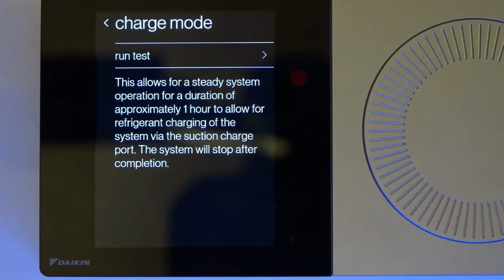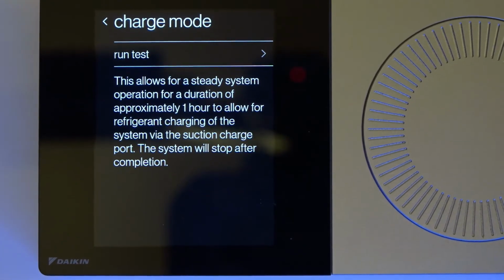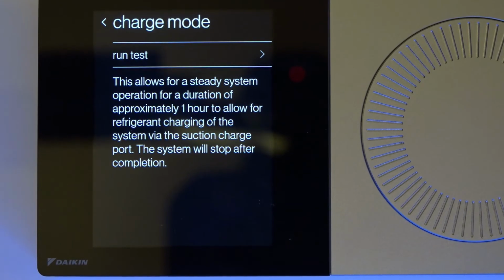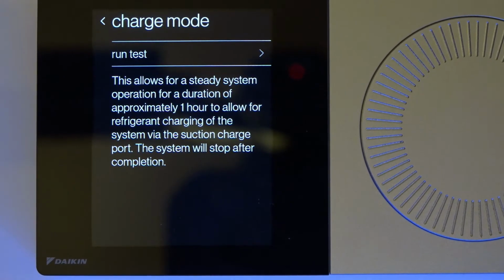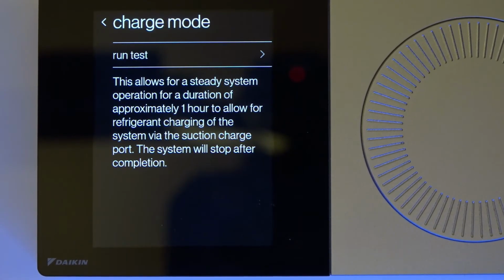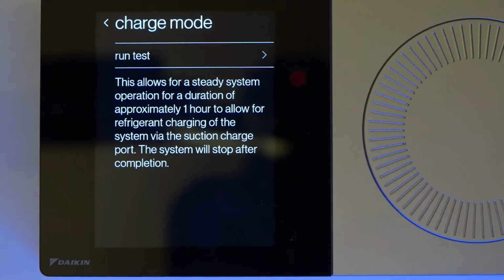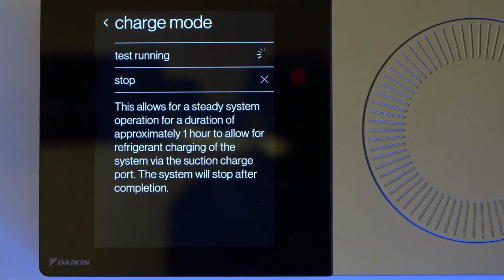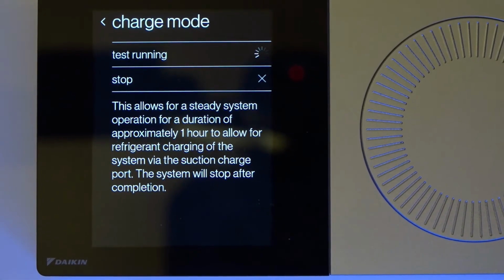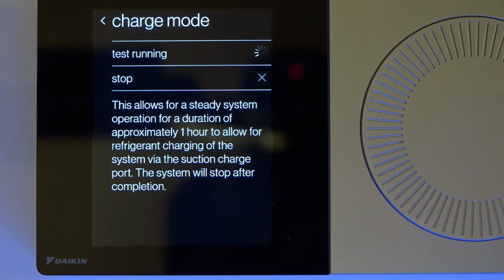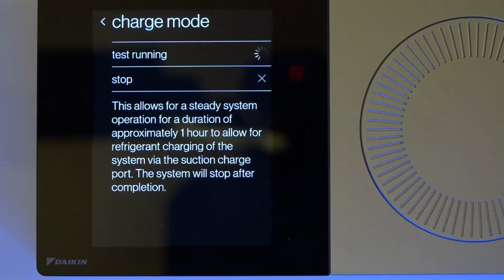And then you know you're ready to move on to the next step. The next step would be charge mode. Now, if you're above 65 degrees ambient temperature and you've got a decent load on the indoor coil, you can run charge mode. When I run charge mode, I just come over here and hit run test. It's going to take about 15 to 20 minutes there again to speed the system up.